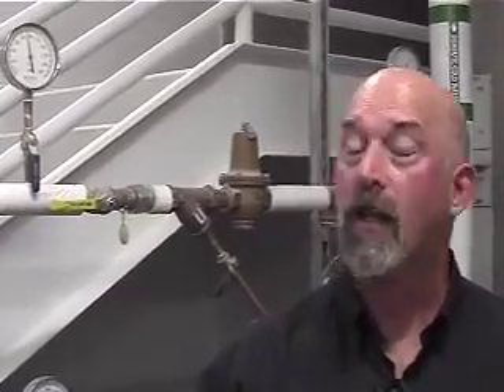F&Ts are a little bit harder to test because they're a continuous drainer. As long as there's condensate coming out of that orifice, it's going to drain it out. One thing you can tell on an F&T is the thermostatic air vent. If that has failed, you're going to hear that high volume of steam. That air vent should normally be closed. When the air accumulates in the top of that trap, it cools and opens up the bellows and lets the air out, the non-condensables. And when steam is in the chamber, it closes the air vent. So you can hear that on startup: you'll hear a large amount of air going through there, and then it should shut off. If it's failed open, you're going to hear really high velocity steam going through that air vent. You're also going to see it out in your vent line. That's a telltale sign of a failed steam trap: a lot of flash coming off of this vent line.